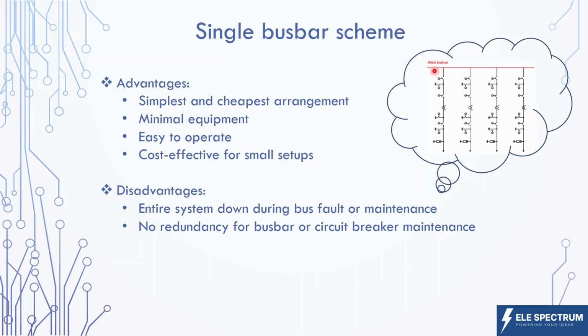And when we talk about the bus bar, suppose we have a fault on this bus bar, the substation needs to be taken out of service till we do the maintenance or repairing work of this bus bar. So we can say this is the least reliable bus bar scheme, but it is very cost effective when we talk about smaller arrangements or distribution systems.